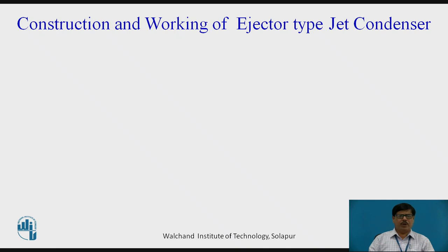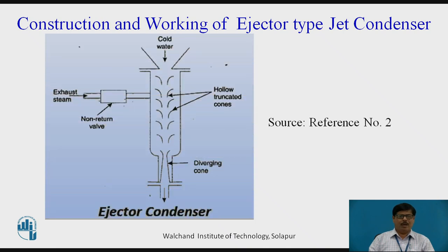Now let us see the construction and working of ejector type of jet condenser. In this figure, we are seeing an ejector type of condenser. The momentum of cooling water is used for ejecting or throwing out the condensate and air in this condenser. We can see that there is a central hollow tube in which hollow truncated cones, which we can also call as converging nozzles, are fixed. The cooling water at a head of around 5 to 6 meters is allowed to flow through these hollow truncated cones.